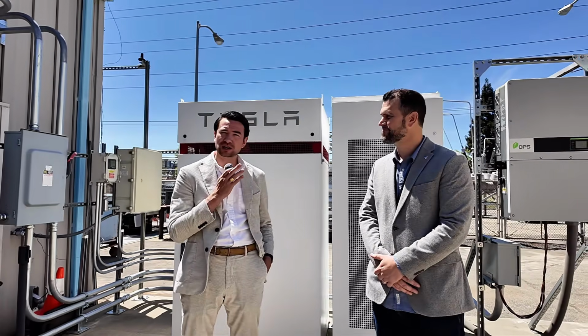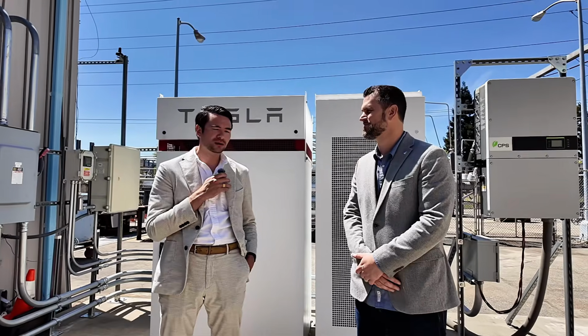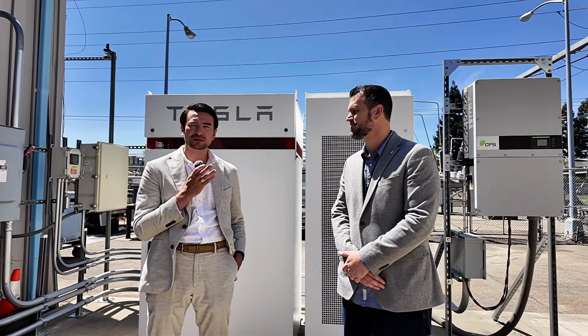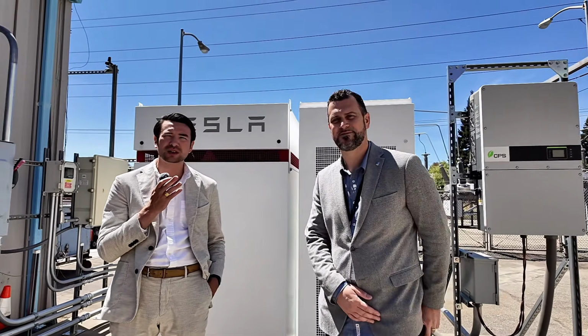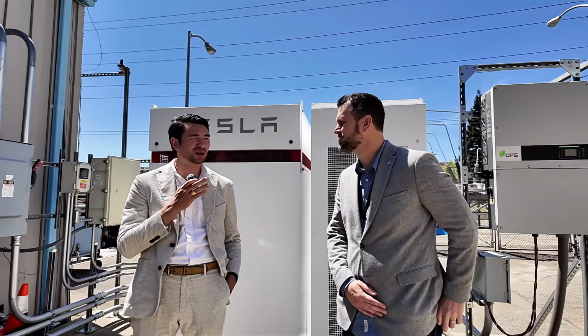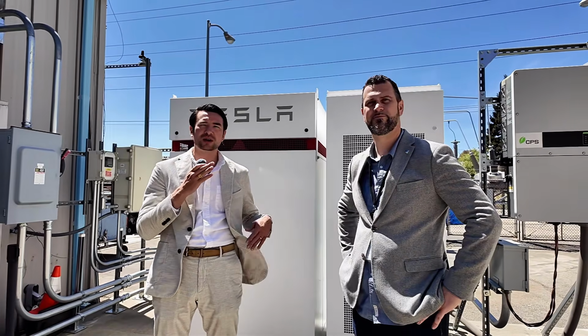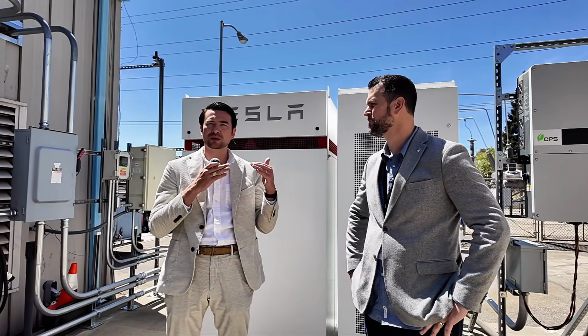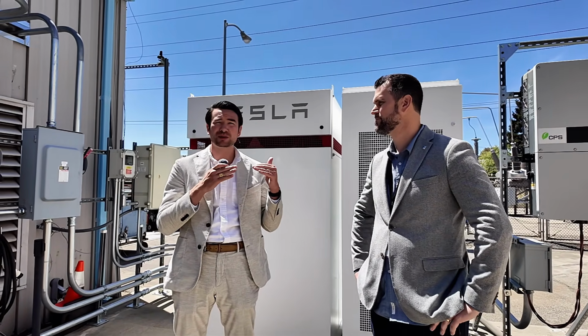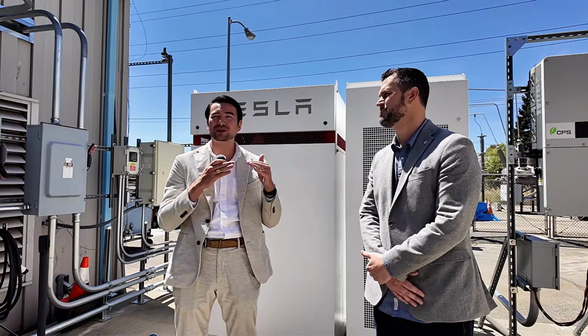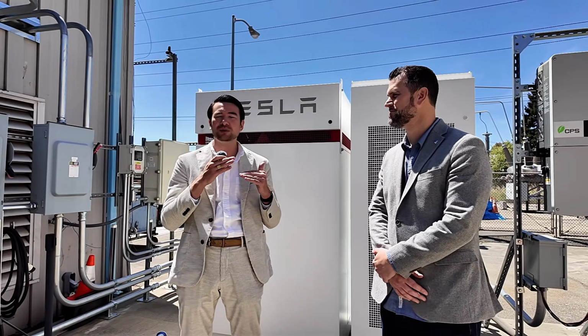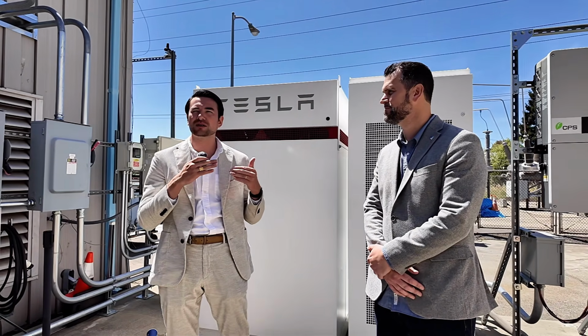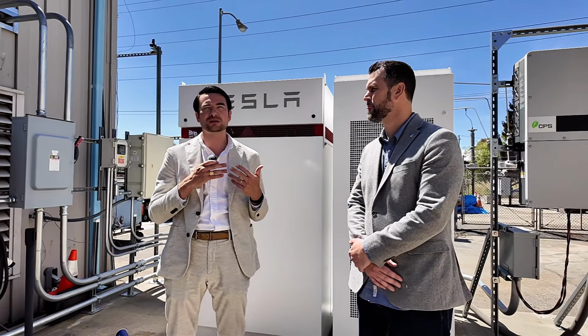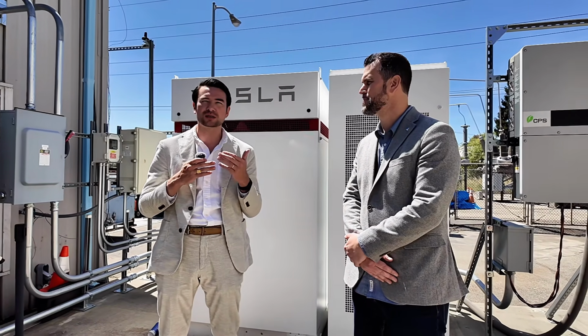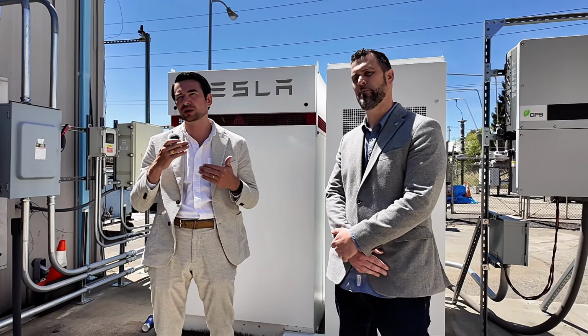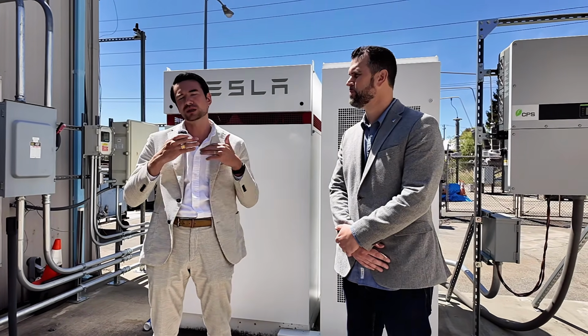There was a DC fast charging site where Tesla was looking for 3.8 megawatts, and we didn't have it. We had something like 400 to 500 kilowatts. That would be the difference of whether or not you would build there at all. But it turns out that by coordinating that with the substation, we could offer the full 3.8 megawatts for 97% of the year. So there's 3% of the year where you're going to be a little bit below 3.8 megawatts, but you'll still be able to run the site. It's examples like that where we're working really hard to get more out of the system we have while we improve it and enable it, and we believe that's what's going to lead to lowering rates.